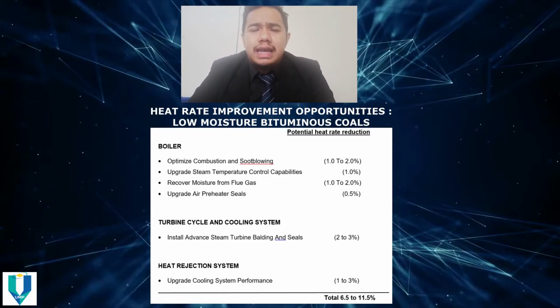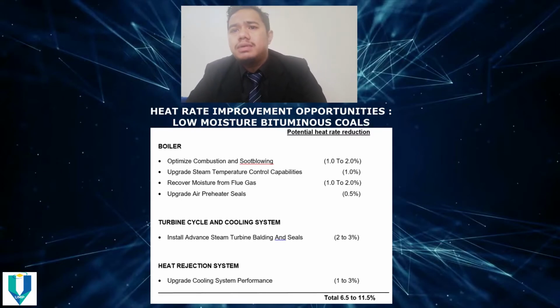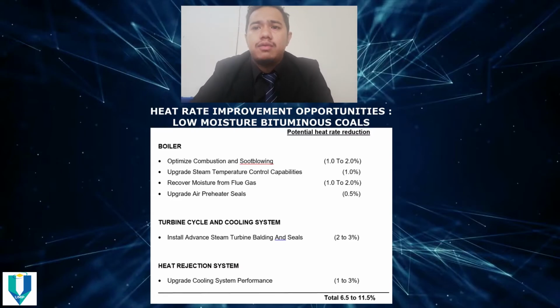For the turbine cycle and cooling system, the potential heat rate reduction from installing advanced steam turbine blading and seals is from 2 to 3%. And for the heat rejection system, the heat rate reduction from upgrading cooling system performance is from 1 to 3%, and the total is from 6.5 to 11.5%.